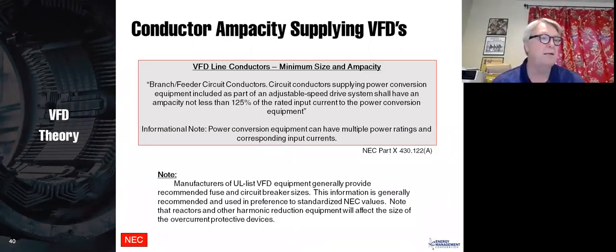Let's talk about ampacity of conductors. According to the National Electrical Code, when you have a motor with a service factor of 1.15 or greater, then the overload protection can be set to trip up to 125%. And because of that, the National Electrical Code requires that conductors from the power system to the motor be sized at 125% of the motor amps. When you put a VFD in there, that does not change. The conductors between the VFD and the motor need to be sized at 125% of the motor full load amps.